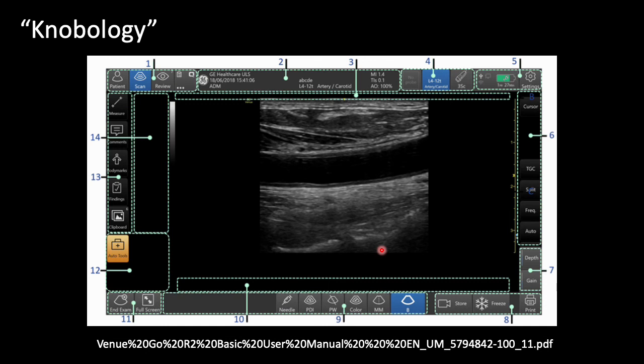One general thing that sonographers do is they put their time gain compensation, the actual sliders, and they'll start them here on the left and do kind of a diagonal down. So low gain, medium gain, high gain, so that at the depths at the farthest end, you're adding gain, you're adding amplitude to your signal to try and help visualize everything better.